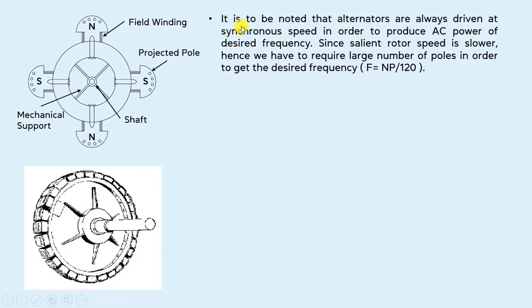It is to be noted that alternators are always driven at synchronous speed in order to produce AC power of the desired frequency. So, alternators always run at a synchronous speed and have a fixed frequency. Since the salient rotor speed is lower, we require a large number of poles in order to get the desired frequency, according to the formula: F = NP / 120.